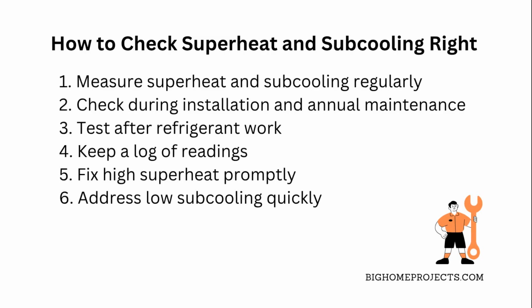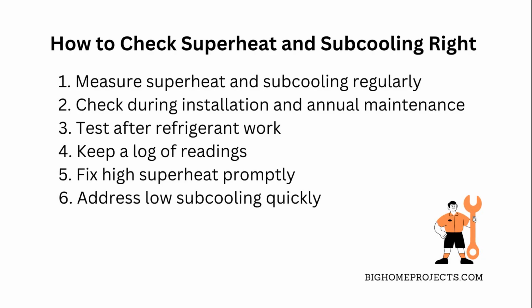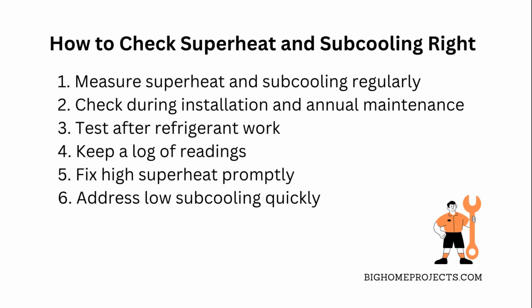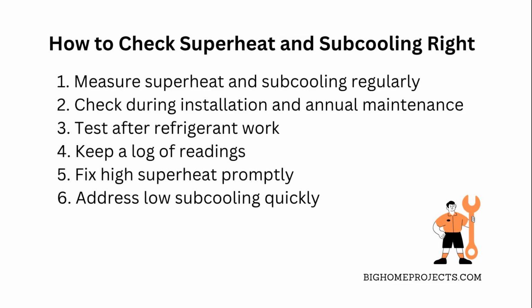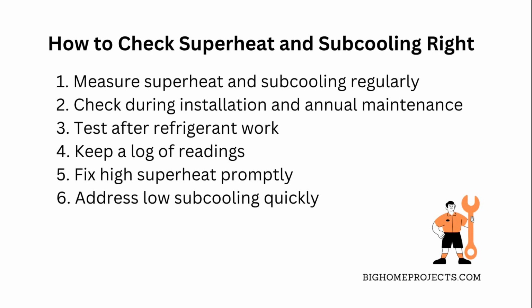If the superheat is too high, it might mean not enough refrigerant, which can cause the compressor to overheat. Too low subcooling could mean a leak or improper charge, so fixing that quick saves you headaches. Just remember, these checks don't take long, but make a huge difference in energy efficiency and system lifespan.